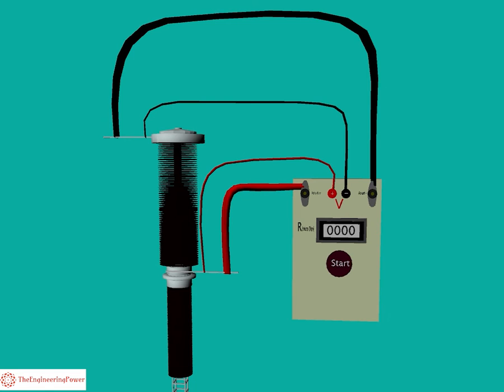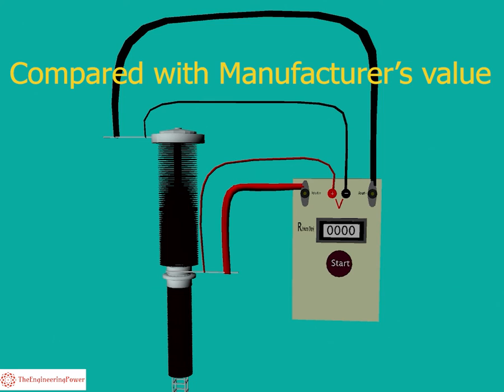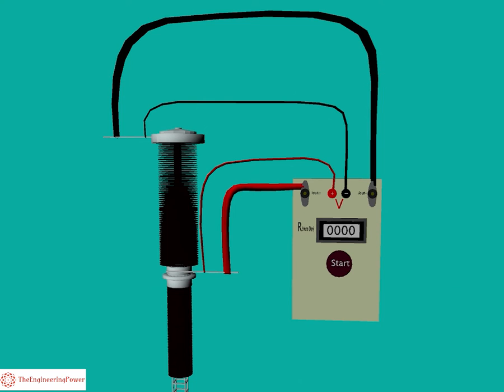The resistance value is calculated using Ohm's law. On the test set, we just press the R button to show the resistance. The measured value of the contact resistance is compared with the value given by the manufacturer. The value is also compared with the previous measured value.